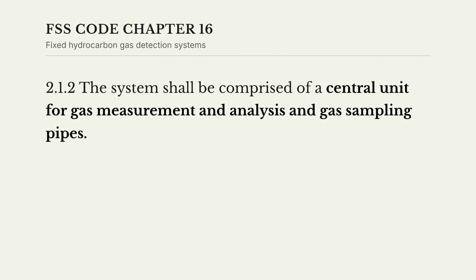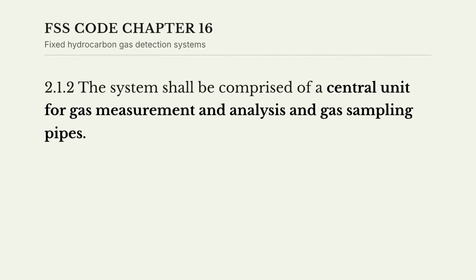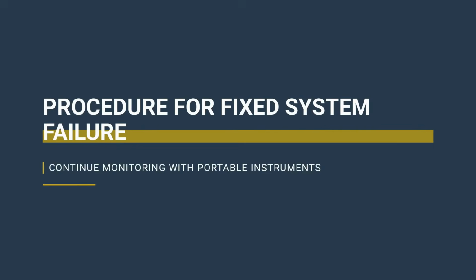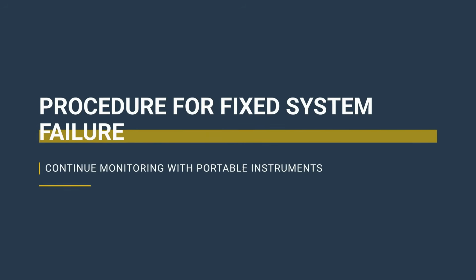The FSS code requires a central unit for gas measurement and analysis connected to these sampling pipes. Each space generally requires a minimum of 2 sampling points, one on the upper part and one on the lower. If the fixed system is out of order, procedures must be in place to continue monitoring with portable instruments.